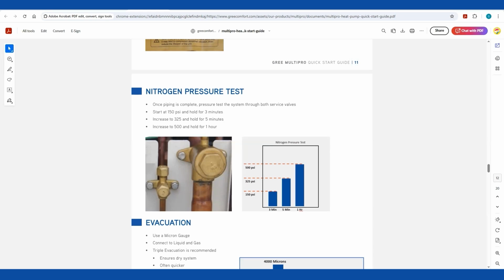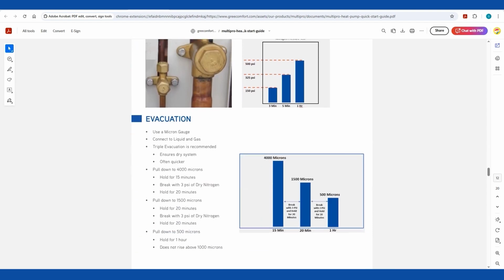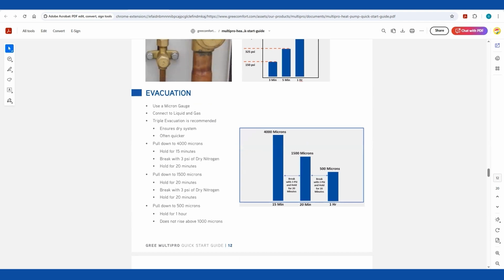So 150 pounds for 3 minutes, then increase to 325 and make sure it holds for 5 minutes, then increase to 500 and hold for 1 hour. Evacuation. We kind of put this together, you know, it's better to make sure you've got a good, clean, dry system.